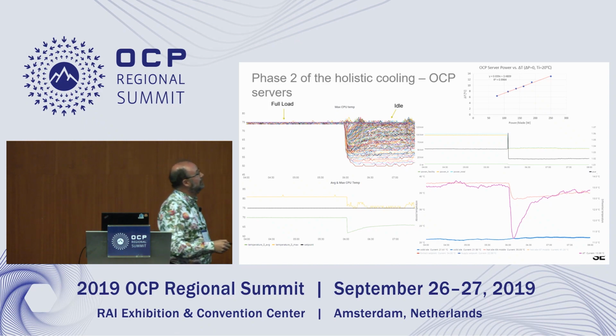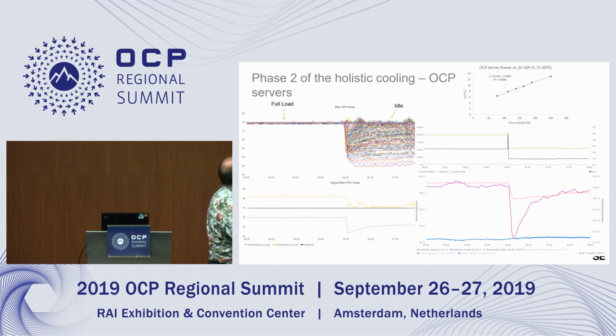You can see the delta T has risen from nearly, I can't quite see it there, let me see it on the screen. It's challengingly small, isn't it? 14 degrees. So even at idle, we're at 14 degrees delta T now, rather than 7. That actually helps. This was an astounding result. When we put full workload on the servers, you could see all the CPU temperatures bunched up at 75 degrees, which is what we wanted to happen. So it maintained the temperature.